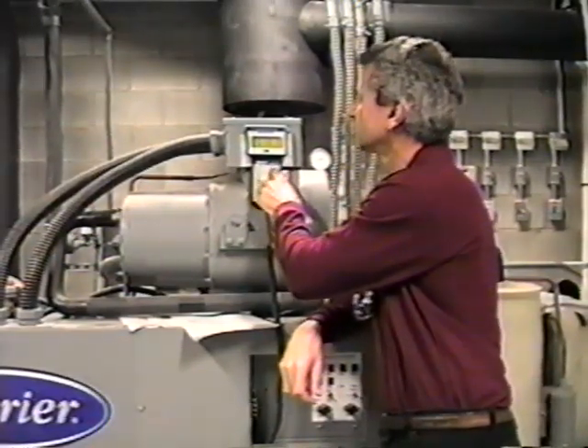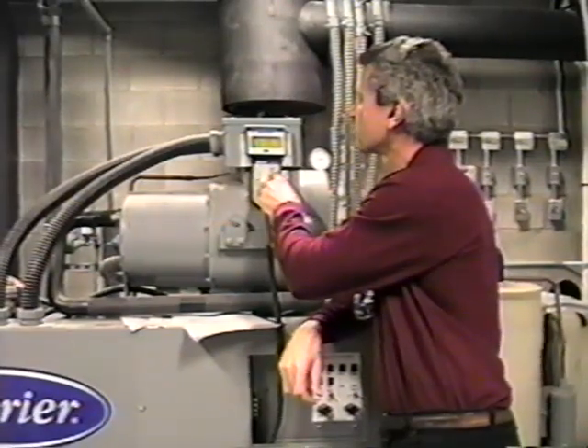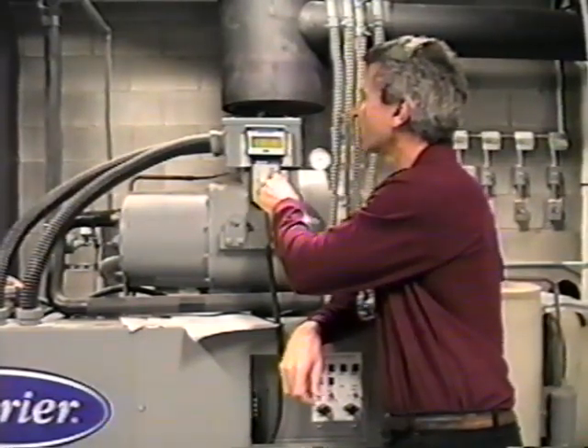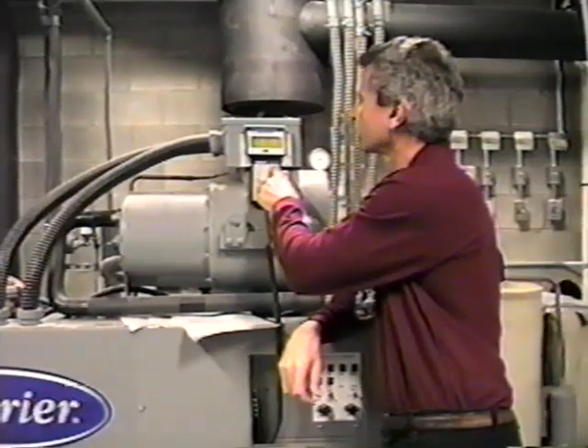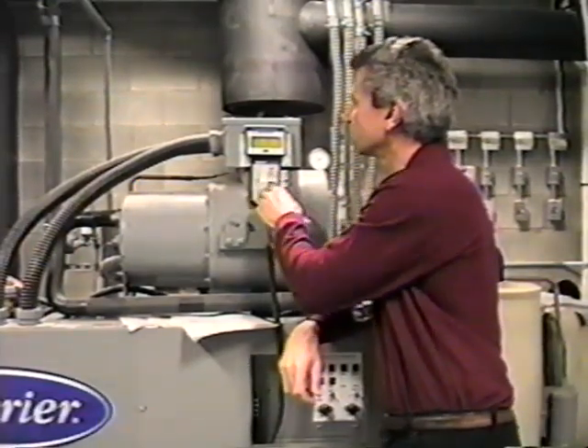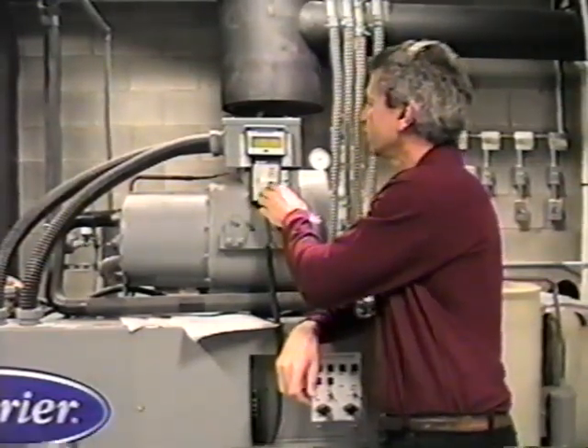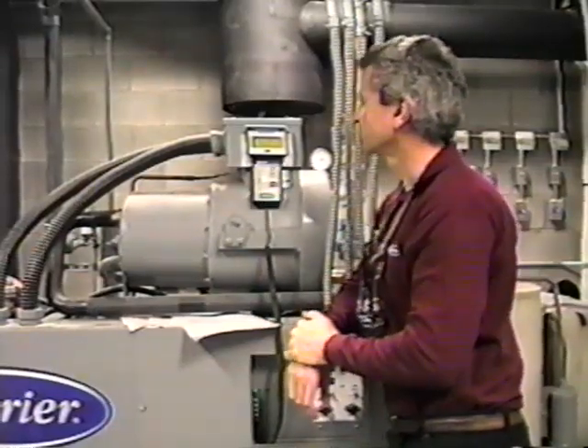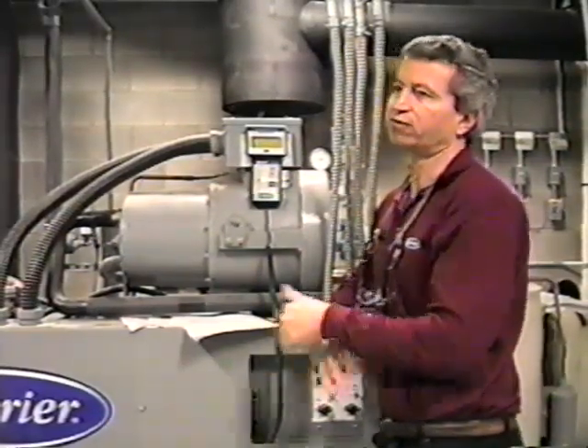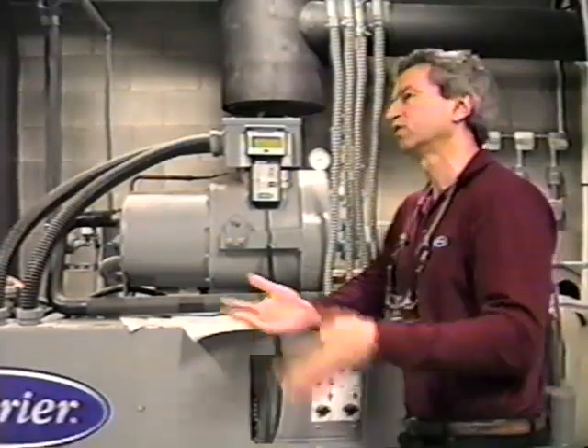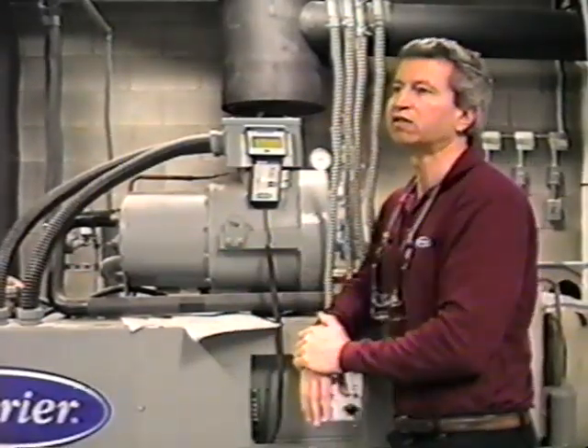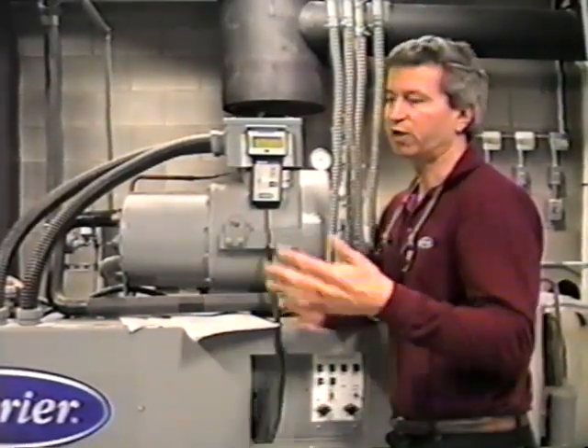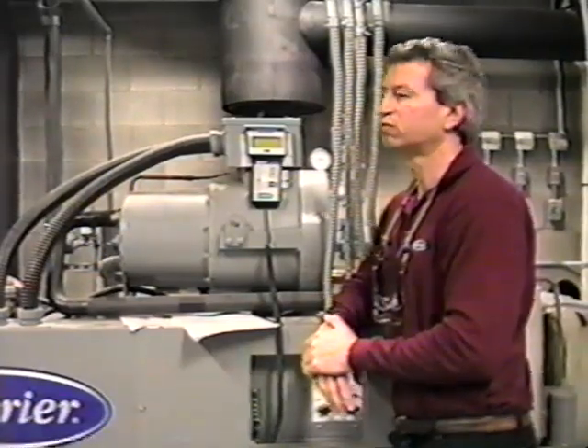Pump outputs, condenser pump, chill water pump, and then there's what we call a Z.CLC. That's what we call a calculated Z factor. It's part of the calculations used to determine how much capacity is needed. That number is going to change depending on how big the load is on the machine.